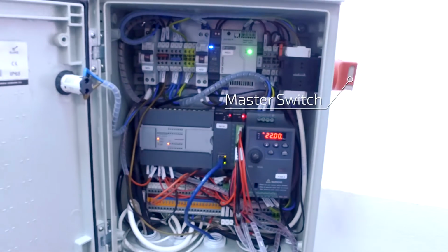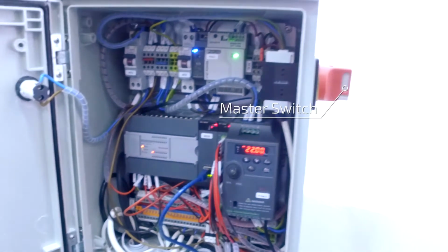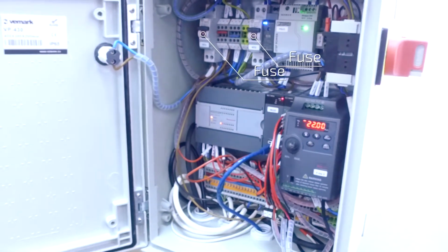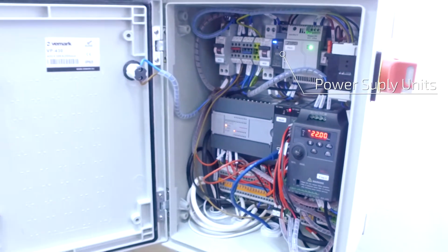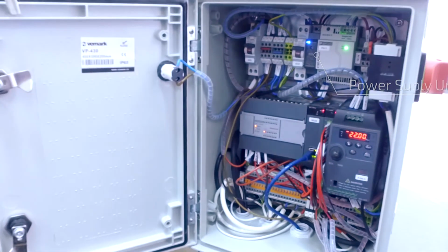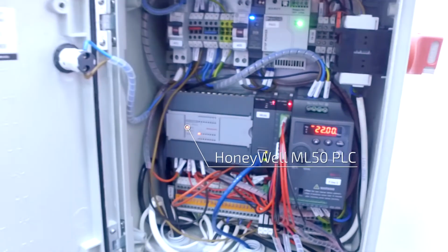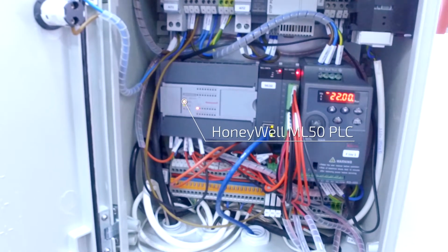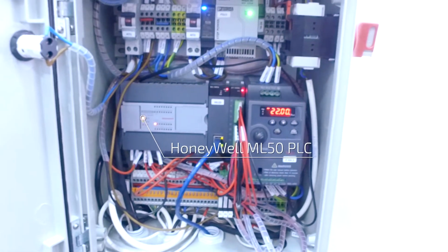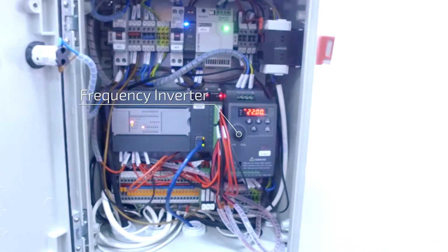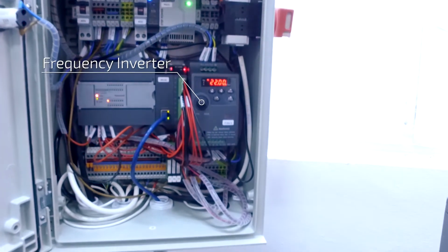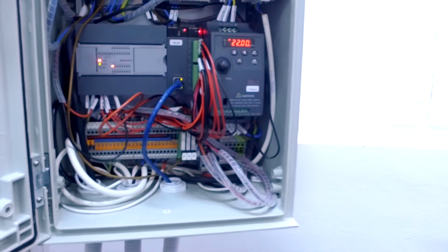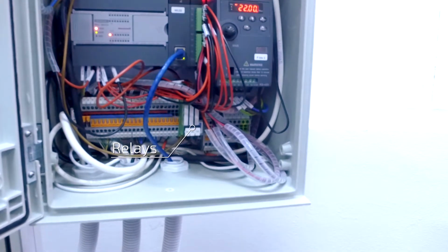The components in the panel include a master switch to turn the panel on and off, current fuses, 12 and 24 volt power supply units, the Honeywell ML50 PLC unit with both analog and digital input outputs, a frequency inverter to control the rotation of the fan, and 3 relays for the infrared heating.